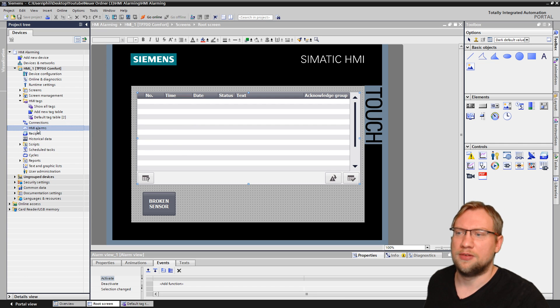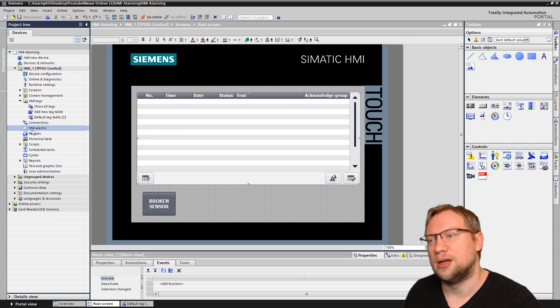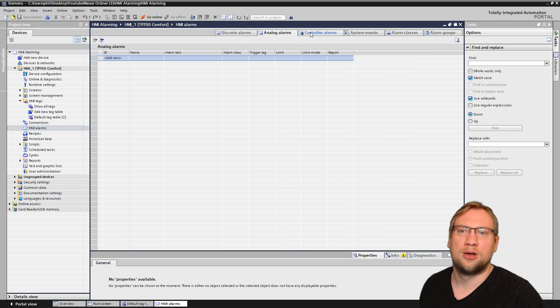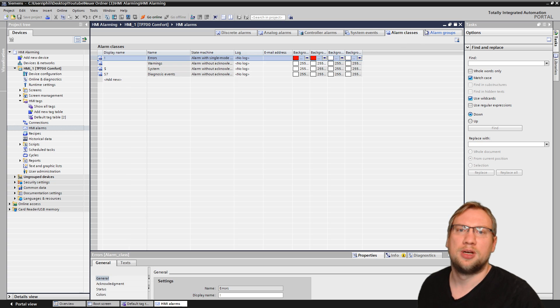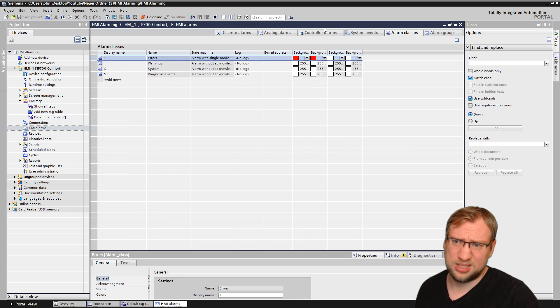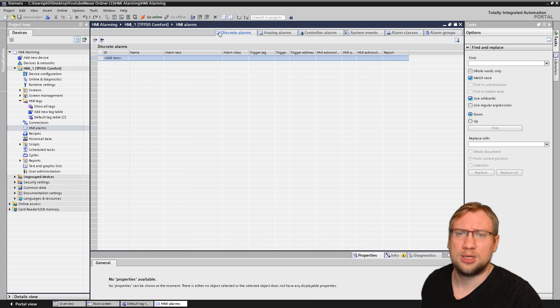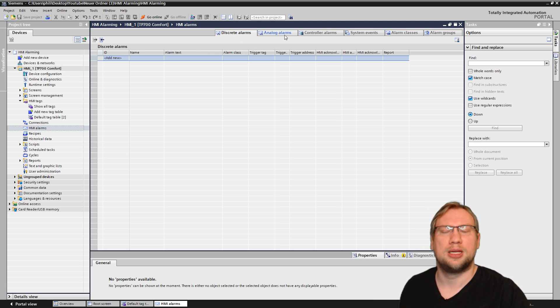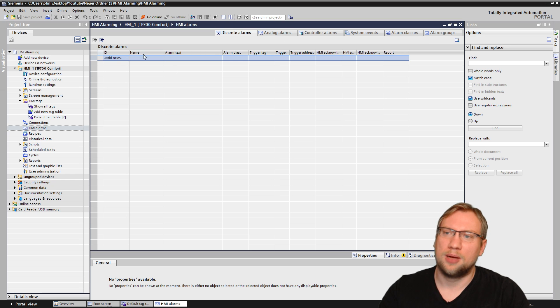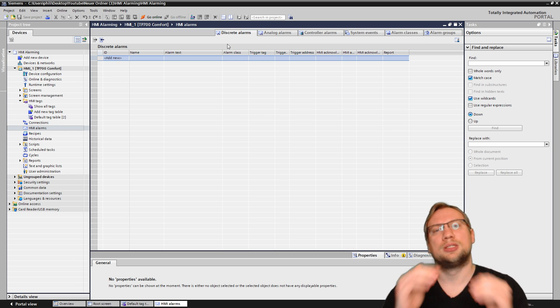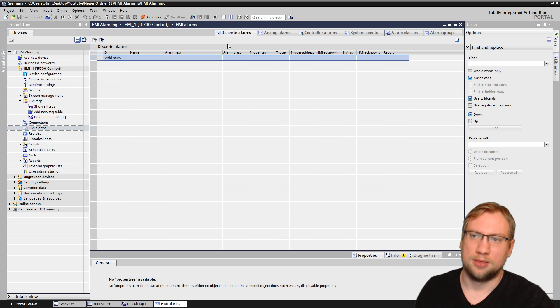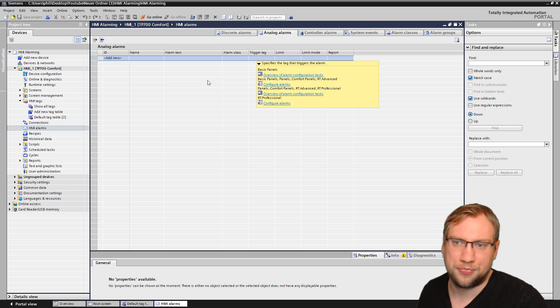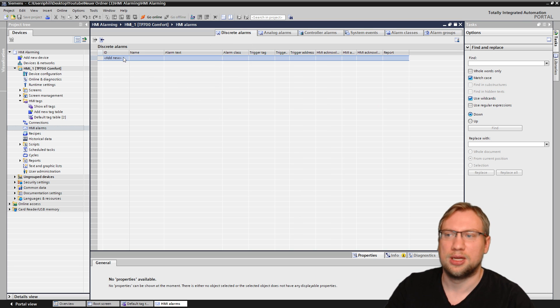We need an alarm definition. On the left side we have 'HMI Alarms.' Inside, we have discrete alarms, analog alarms, controller alarms, system events, alarm classes, and alarm groups — there's already a lot pre-configured. I'll cover discrete alarms and analog alarms here. Discrete means something is on or off — a boolean state. Analog alarms ask whether a value is greater than a certain number, so they work with actual numeric values.